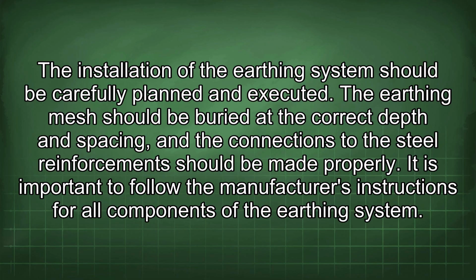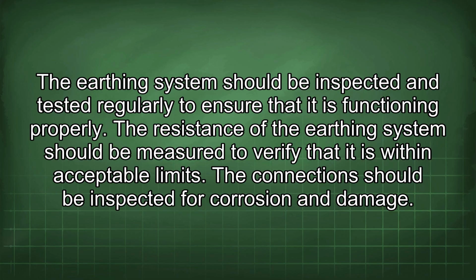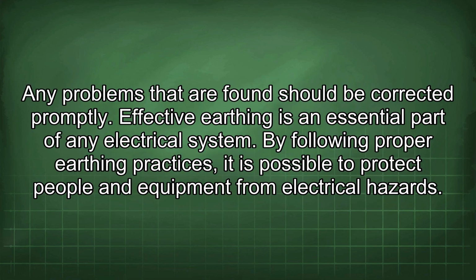The earthing mesh should be buried at the correct depth and spacing, and the connections to the steel reinforcement should be made properly. It is important to follow the manufacturer's instructions for all components of the earthing system. The earthing system should be inspected and tested regularly to ensure that it is functioning properly. The resistance of the earthing system should be measured to verify that it is within acceptable limits. The connections should be inspected for corrosion and damage. Any problems that are found should be corrected promptly.